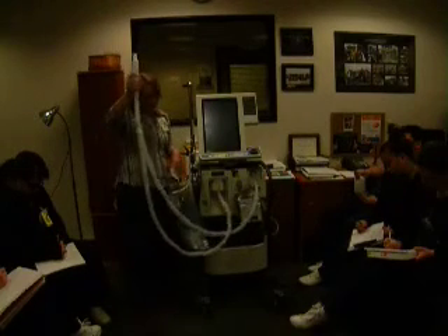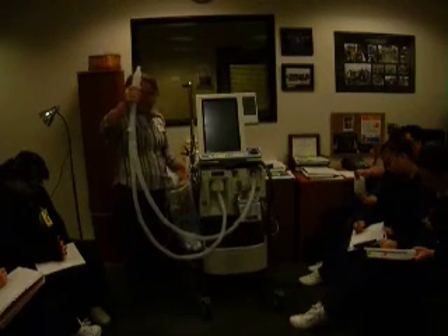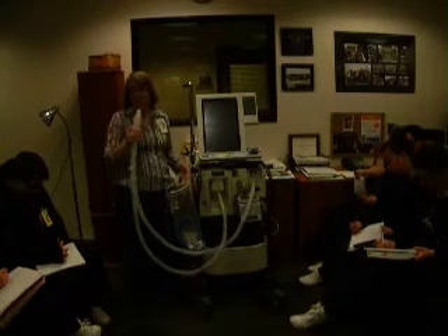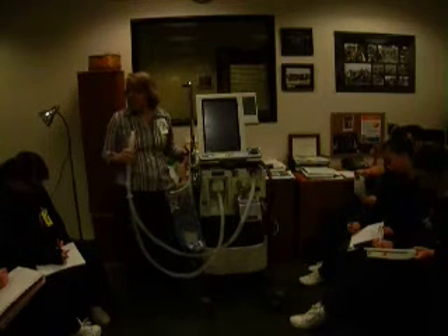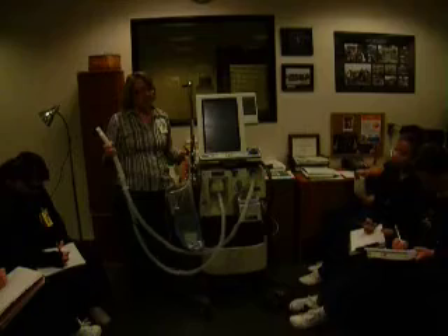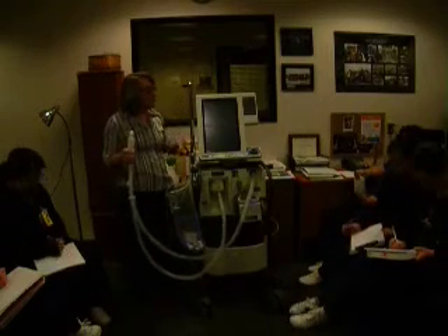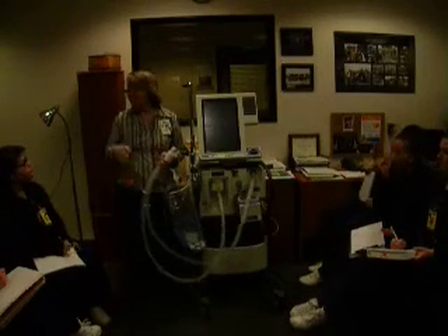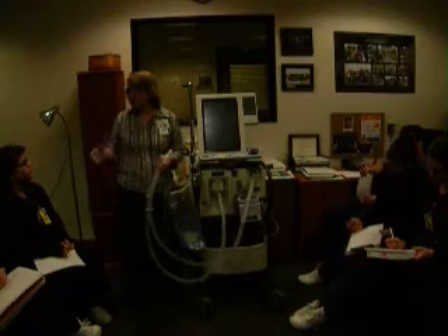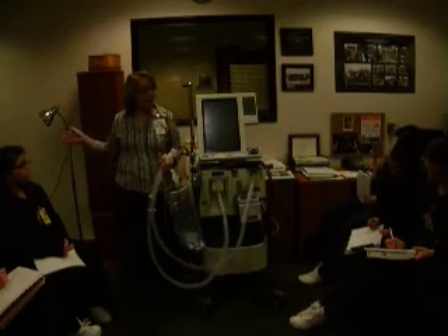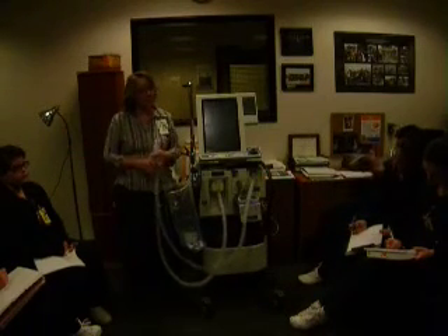So let's say that something malfunctions on the ventilator inside, and we don't know what it is, but it's a serious error and the vent's going to shut down. Well, it's hooked to a patient. If the vent shuts down, your patient's not going to breathe. So it will open a safety valve. The safety valve will allow the patient to at least breathe room air. So it opens up the ventilator to room air until somebody comes over and fixes what the problem is.